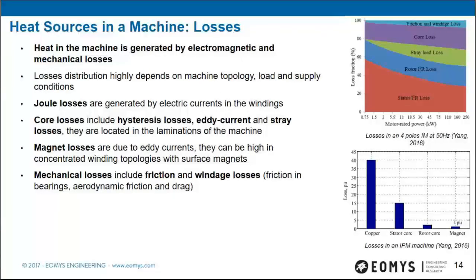Heat in an electric machine is generated by electromagnetic and mechanical losses. The losses distribution depends on the machine topology, load, and supply conditions. There are four main kinds: Joule losses from electric currents; core losses including hysteresis, eddy current, and stray losses in the laminations; magnet losses due to eddy currents in the magnets; and mechanical losses including friction and windage.